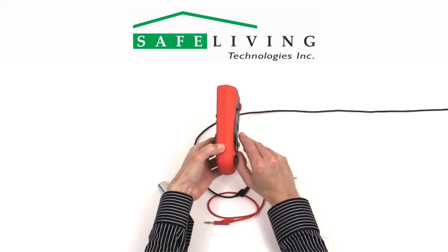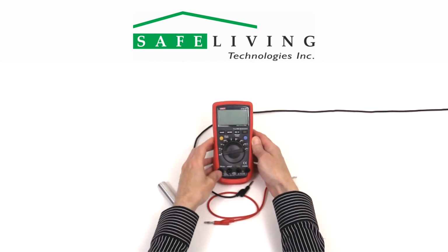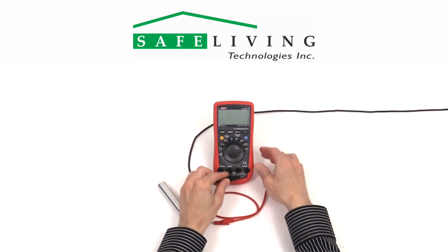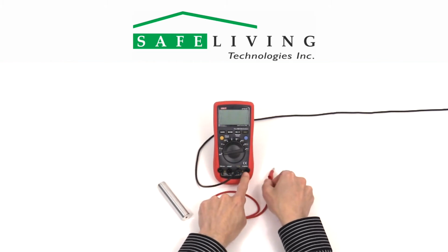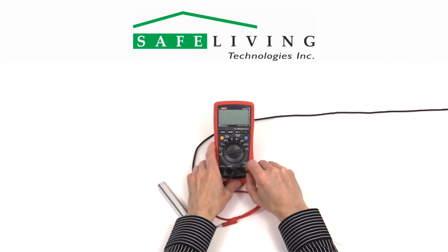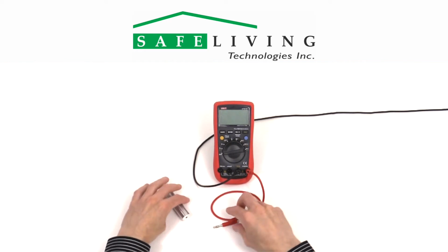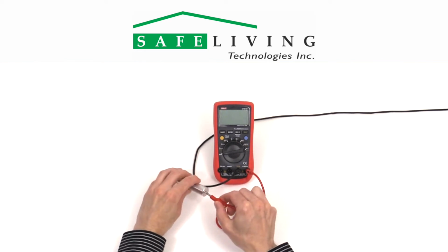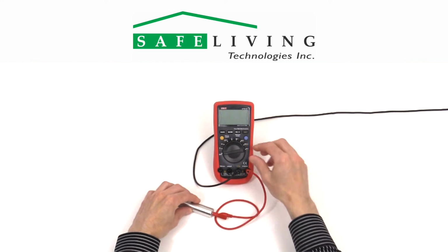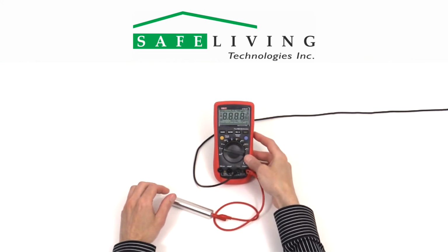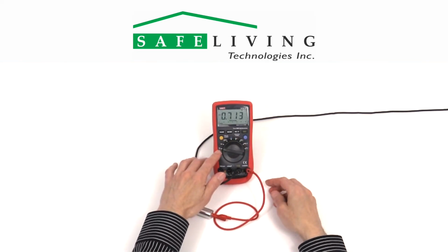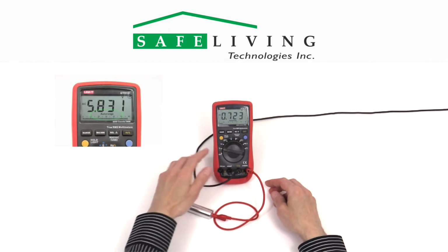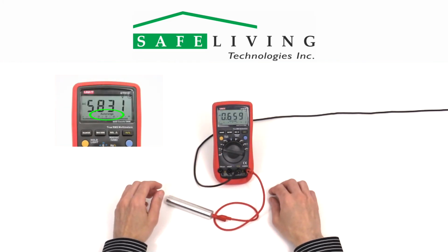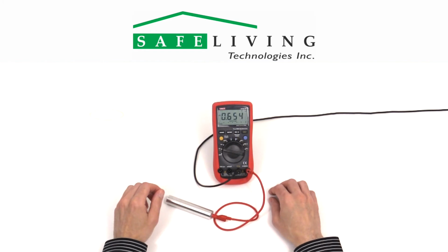With a proper ground connection, prepare the meter and hand probe by connecting the black ground cable here and the red hand probe here as shown. The other end of the red cable inserts into the probe as shown. Turn the meter on into the AC voltage function as shown. Note that this meter is auto-ranging by default, so it will automatically adjust itself to the appropriate voltage range. Now we're ready to accurately measure a true RMS body voltage.